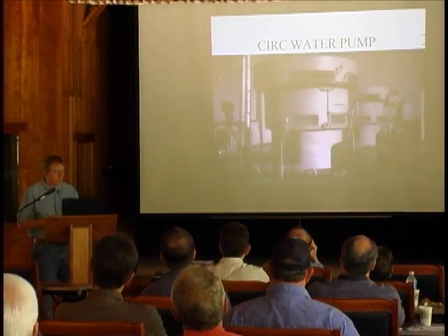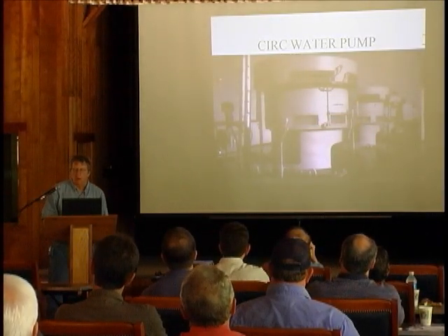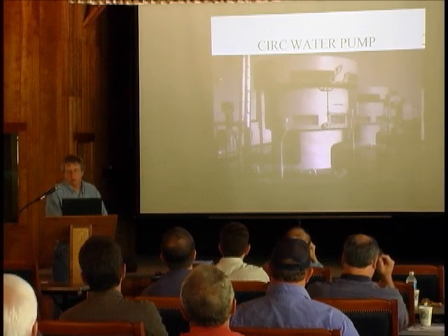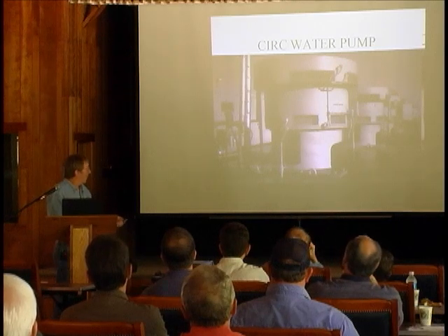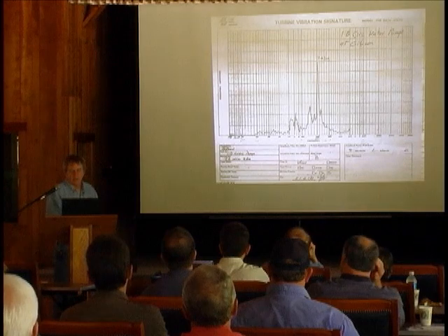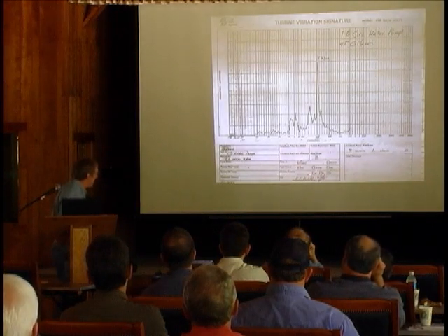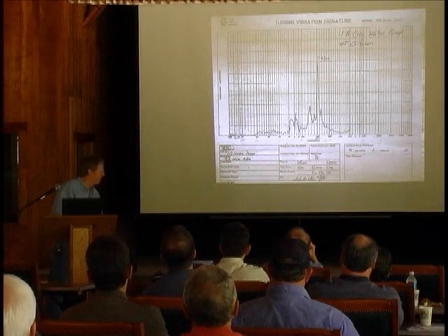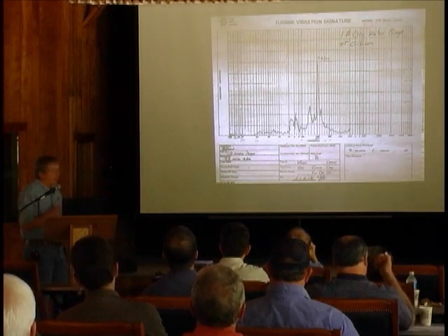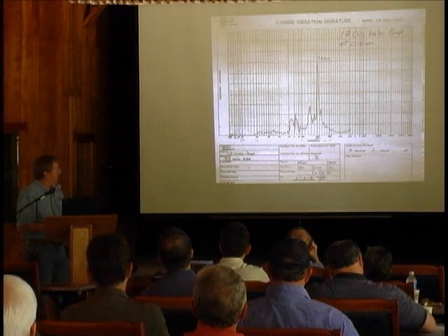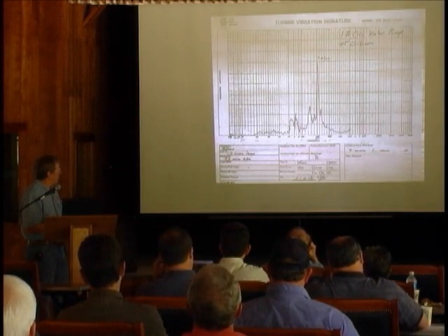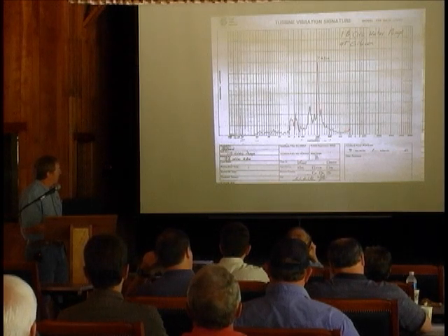Okay, go to a circulating water pump. These are large vertical pumps, and they pump water through the condenser at a power plant. And they're having trouble tearing these things up. And this is an old reading. What's this? 1980. I have indeed been doing this a long time. This was an old IRD 350 with a strip chart. And this is just a broadband vibration. Here's one thing that pops up here.